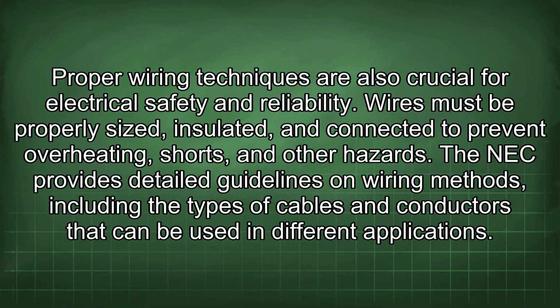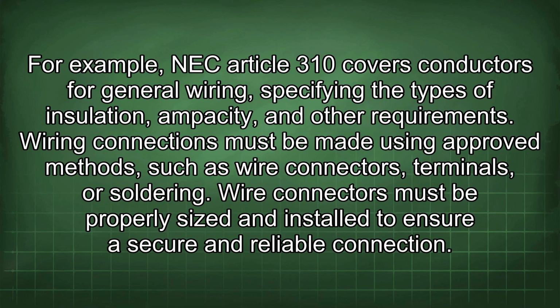Proper wiring techniques are also crucial for electrical safety and reliability. Wires must be properly sized, insulated, and connected to prevent overheating, shorts, and other hazards. The NEC provides detailed guidelines on wiring methods, including the types of cables and conductors that can be used in different applications. For example, NEC Article 310 covers conductors for general wiring, specifying the types of insulation, ampacity, and other requirements. Wiring connections must be made using approved methods such as wire connectors, terminals, or soldering. Wire connectors must be properly sized and installed to ensure secure and reliable connection.